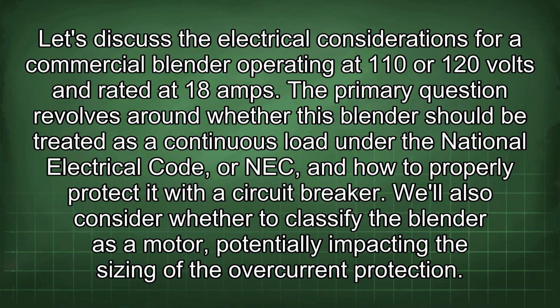Let's discuss the electrical considerations for a commercial blender operating at 110 or 120 volts and rated at 18 amps. The primary question revolves around whether this blender should be treated as a continuous load under the National Electrical Code, or NEC, and how to properly protect it with a circuit breaker. We'll also consider whether to classify the blender as a motor, potentially impacting the sizing of the overcurrent protection.